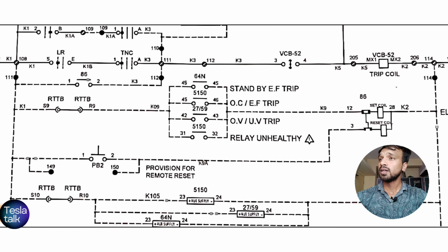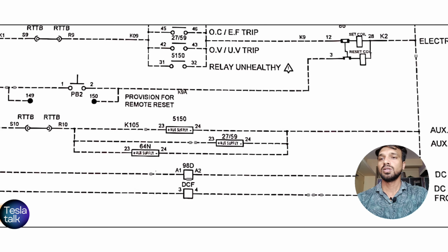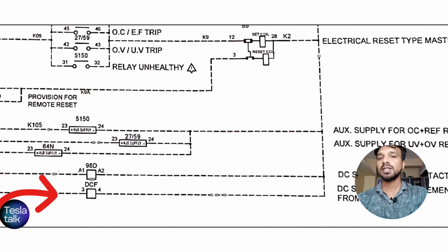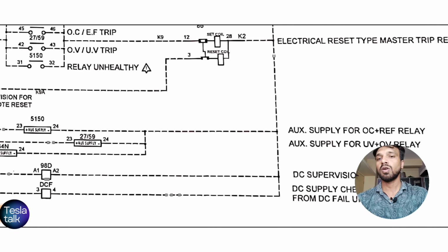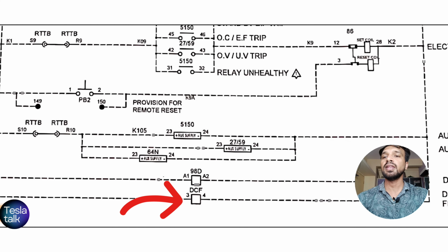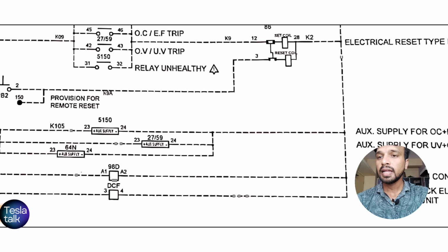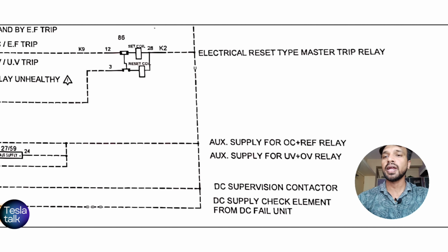Then there are some supervisory circuits. The supervisory section checks the health of the DC supply and the other circuit elements. The DC supervision contactor checks the health of the control supply. If the DC supply is lost, then the supervision circuit sends an alarm. The auxiliary supply ensures that the protective relays have power to function. So this one is the DC supply check element from the DC fail unit. This one is the DC fail relay. Then 98D is the DC supervision contactor.